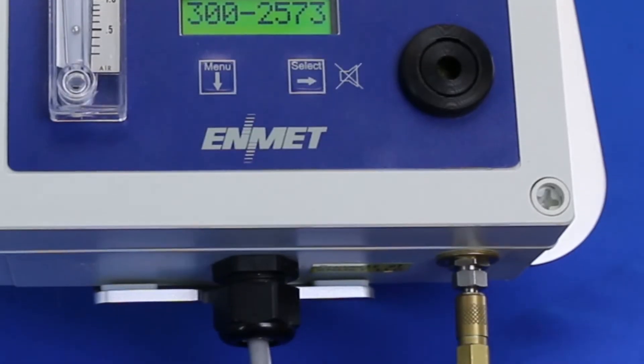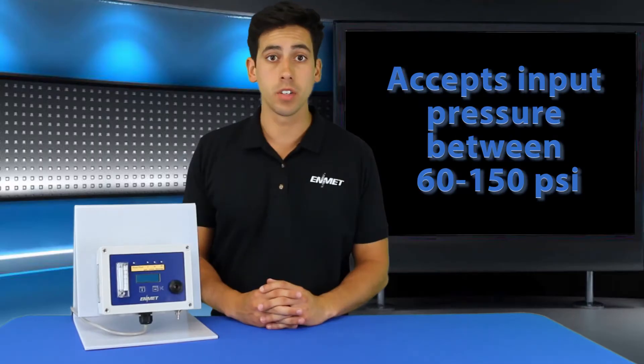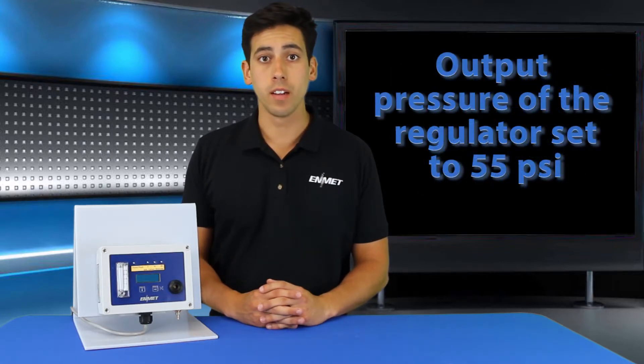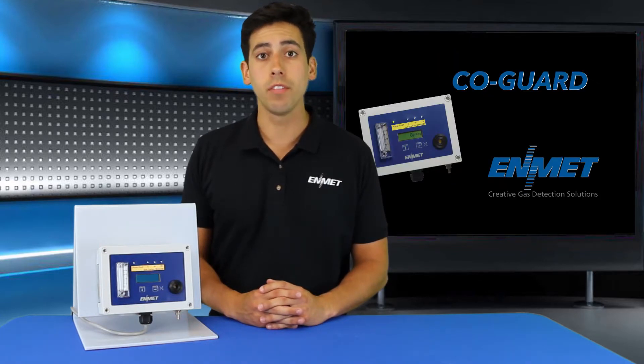The standard regulator provided with the CO-Guard is designed to accept an input pressure between 60 to 150 psi. The output pressure of the regulator is set to 55 psi to provide a flow rating of around half a liter per minute as viewed on the flow meter.